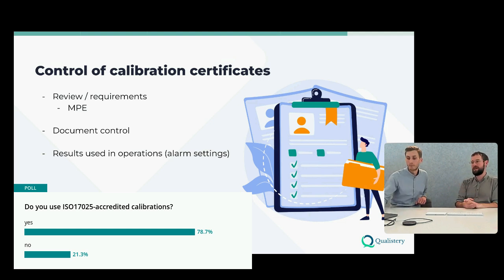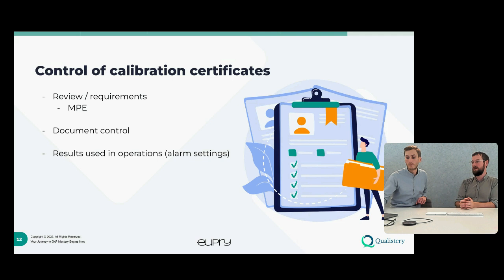I think a good point is that often accreditation is associated with high levels of quality in terms of calibrations. It's a high level of quality in the sense that those are controlled, but actually the major point is that the stated calibration uncertainty has been proven and has been audited. You can have a calibration uncertainty of 100 degrees and still be accredited. Those are really not correlated, but it basically means you can trust the results and you can trust the calibration uncertainty. Hence you actually have a decent understanding of what you're looking at when you're looking at a calibration certificate.